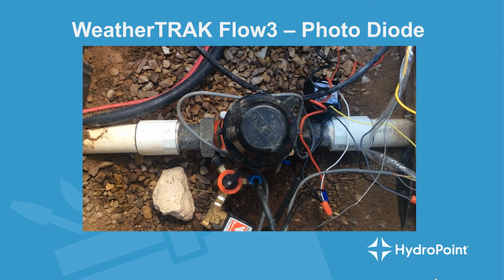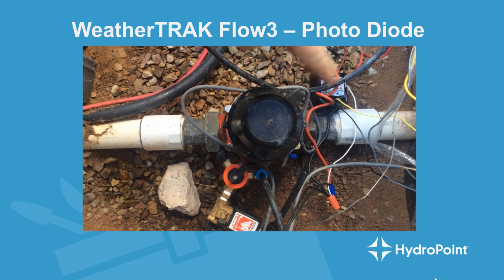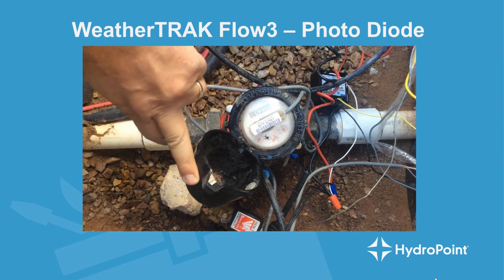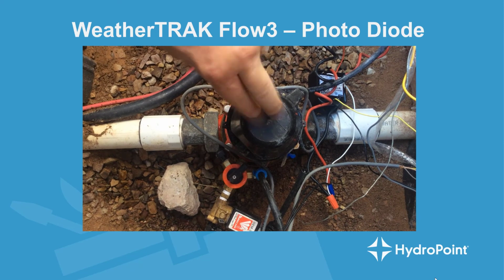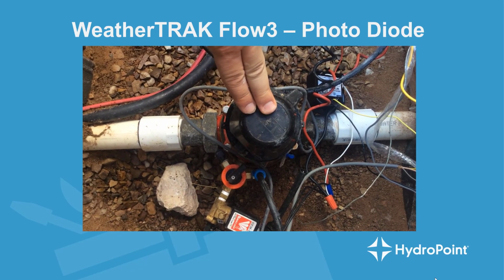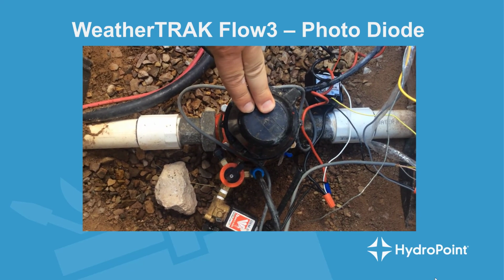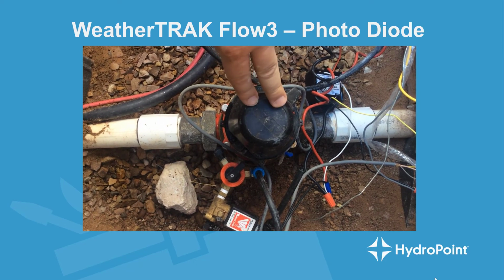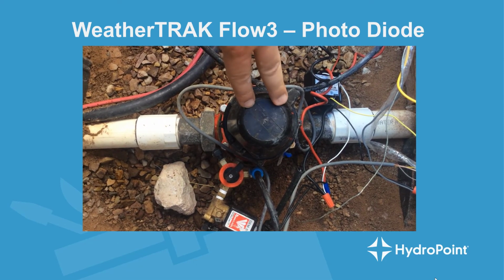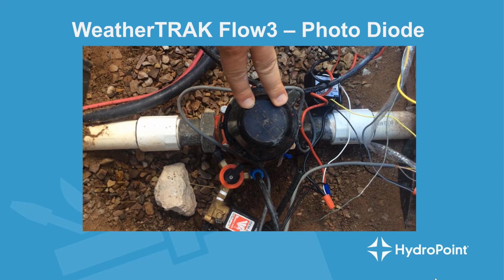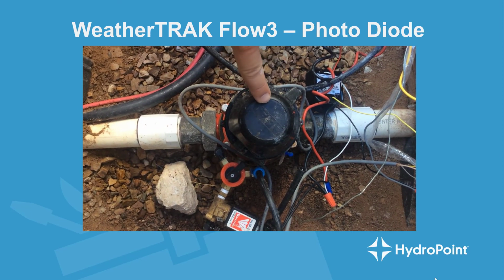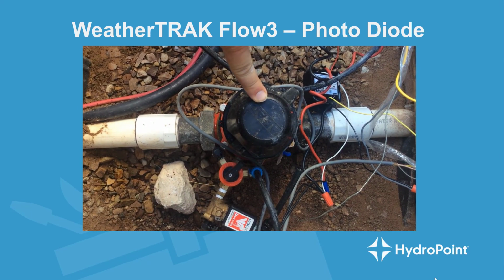Alright, so on a photodiode flow sensor, while we're looking in its valve, we want to make sure that the photodiode is covered, or the valve cover is closed, because that photo selector switch is using the light, so any light pollution will affect the reading of the flow sensor. So whenever you want to use the flow sensor, make sure the cover is closed.